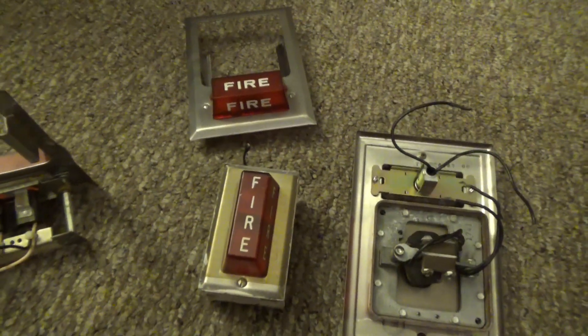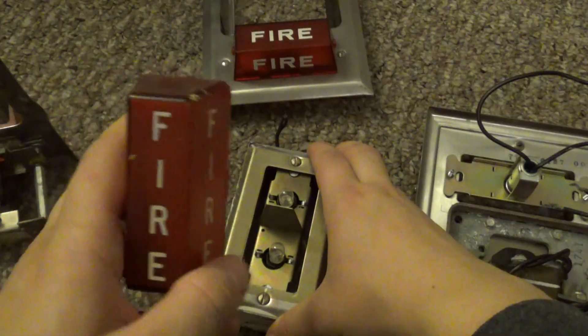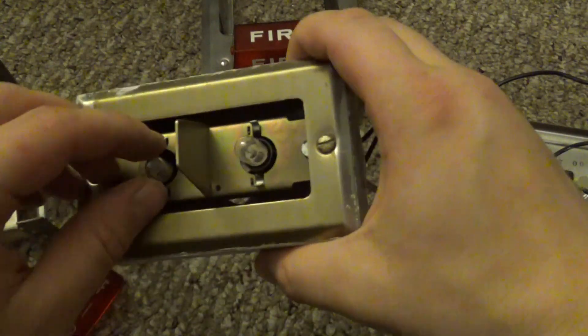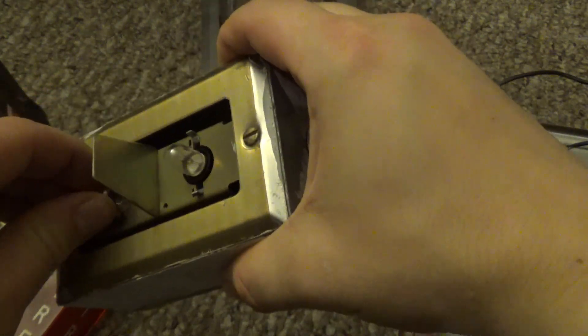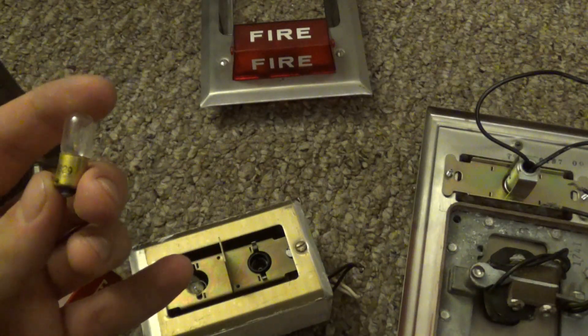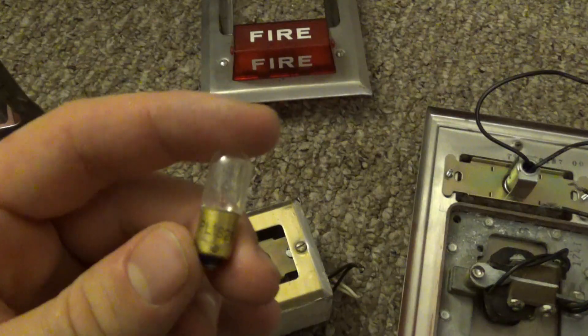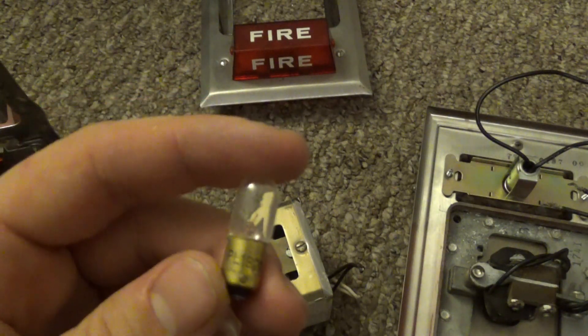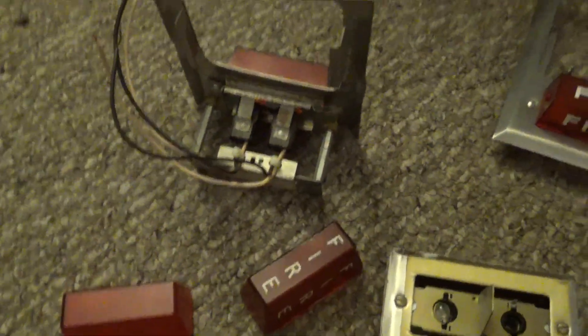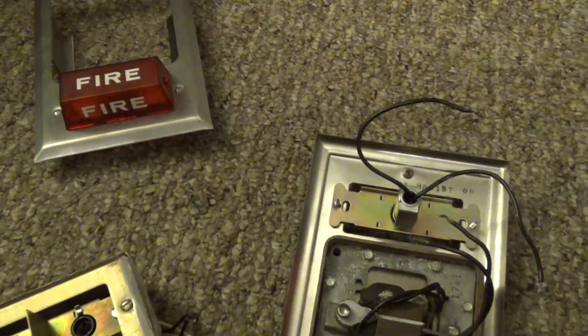And now on to the remote light version — this one is a couch Exide remote light. This one also has a clip-on vertical fire lettering lens and two small bulbs. These take PL 1822 bulbs — the ones in here are 1829s, basically the same as a 1822. These are 24 volt bulbs. The regular 4050-80 series plates also take these smaller bulbs, whereas the 4050-83 and the couch Exide light plate take bigger bulbs, and the 4051-60 series also takes the screw-on bigger bulbs.